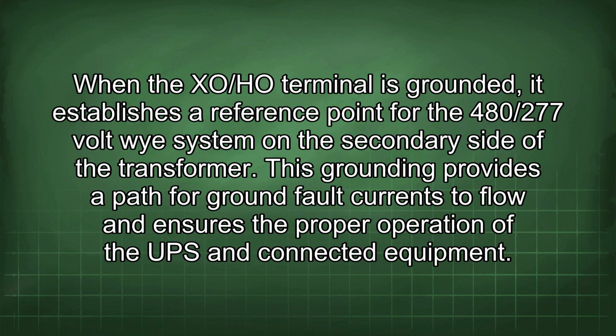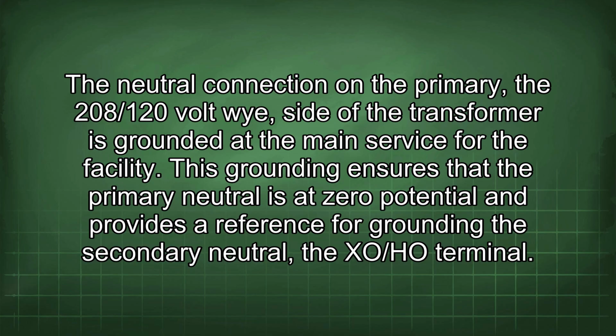When the XO/HO terminal is grounded, it establishes a reference point for the 480/277 volt Y system on the secondary side of the transformer. This grounding provides a path for ground fault currents to flow and ensures the proper operation of the UPS and connected equipment.